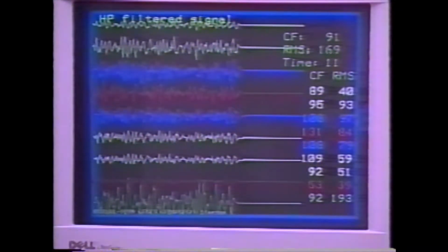The position of the diaphragm along the electrode array is determined by systematically cross-correlating EMG signals from every second pair of electrodes. The cross-correlation technique can be successfully used because the EMG signals obtained below the diaphragm are reversed in polarity from the signals obtained above the diaphragm and hence will correlate negatively. The most negative correlation coefficient represents the region where the diaphragm is located along the electrode array. The blue signals demonstrate the 2 most negatively correlated signals in this example. This technique ensures that the EMG array and the gastric and esophageal balloons are in appropriate positions.